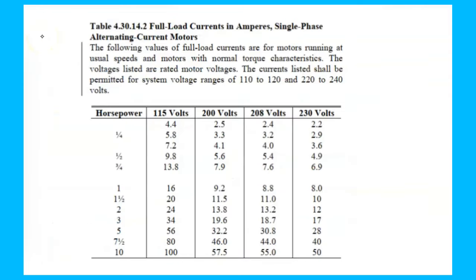Ang sabi sa PEC 2017 table 4.30.14.2, or yung full load currents in amperes for single phase alternating current motors. So from this column, ito yung horsepower, meron tayong 1/4, 1/2, 3/4, 1, 1.5, 2, 3, at saka 5. Ito lang yung mga commonly used HP aircon unit. So the first, the second column is 115 volts, 200, 208 at saka 230. So dito tayo mag-focus sa column na to.